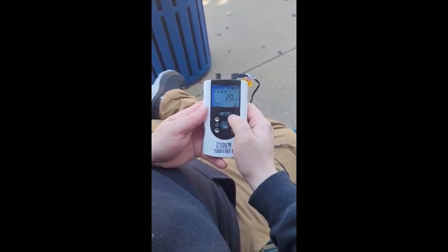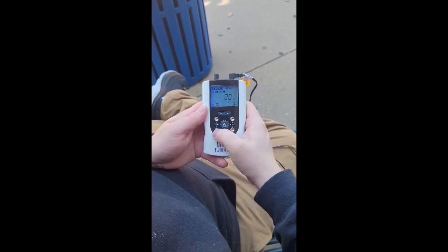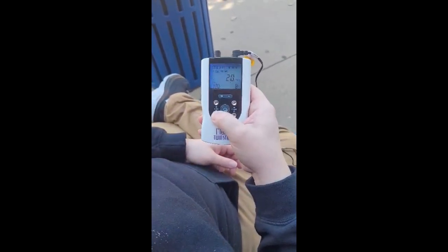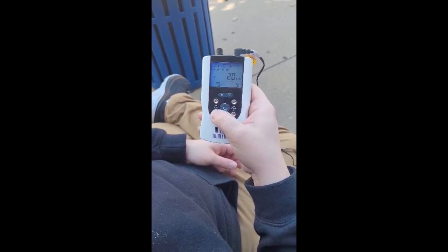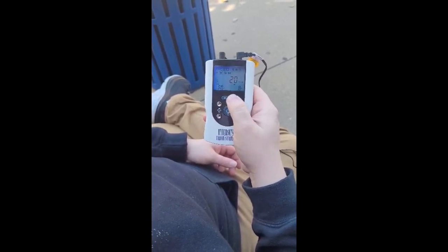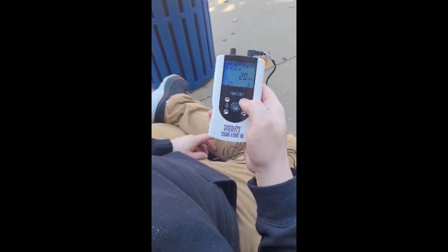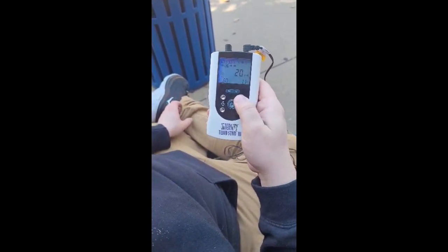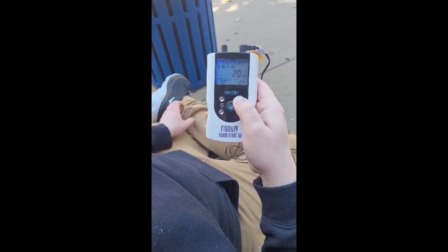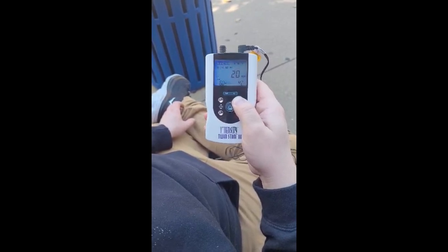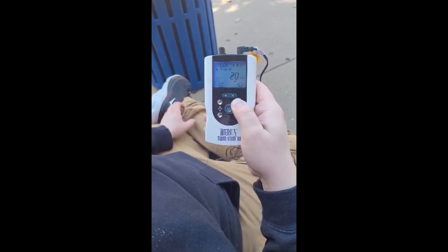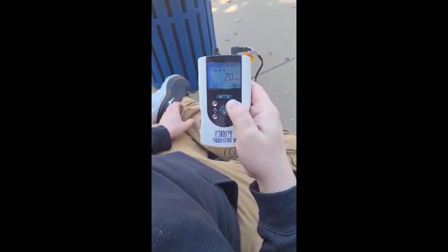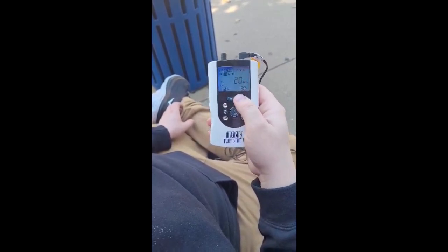And then you're going to hit select again, you're going to change the pulse duration. Since this is acute, it's going to be 60 to 100, so I'd bring it to 60 for patient comfort. Start with that. And then pulses per second, since this is also acute, you're going to want to do 80 to 150. I would start at 80, so I'm going to bring this up to 80. Okay. And then that's how you set that.